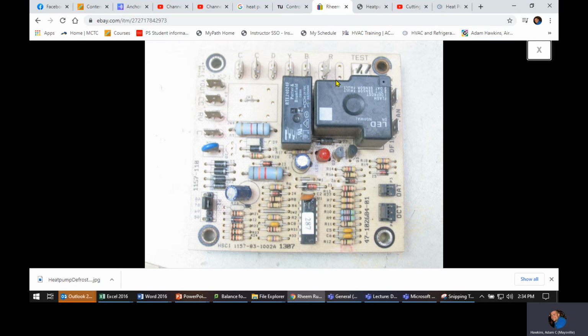Now on this one, if you look on the side over here, you can see where it says DF1 and DF2. So this is your defrost for your fan. This is bringing it in, bringing it out. You just got an L1 or whatever it is, your power wire coming in, power wire going out, and then going to the fan. So power coming in, breaking it. This is normally closed. The only time it opens is when the system goes into defrost. So there are times when this switch will go bad inside here. So if you ever have a fan that's not running in air conditioning, before you assume that the motor's bad, because don't assume anything, check this.